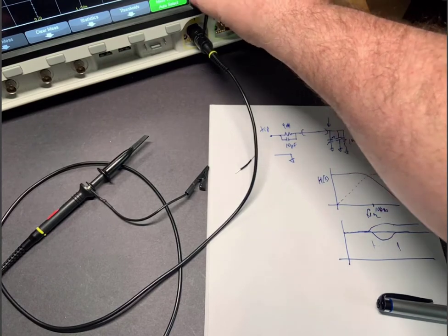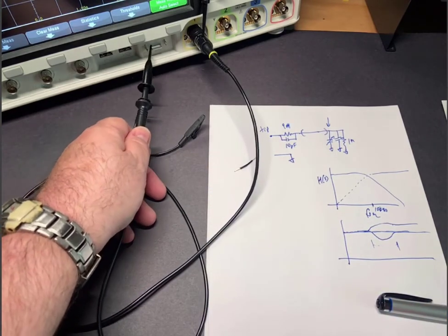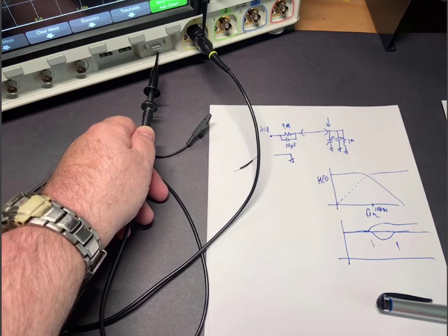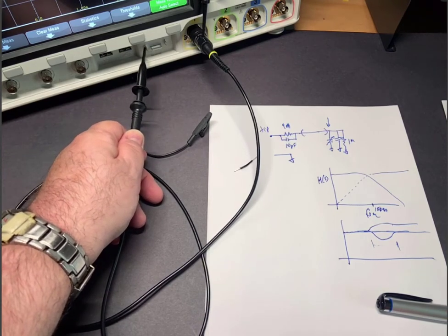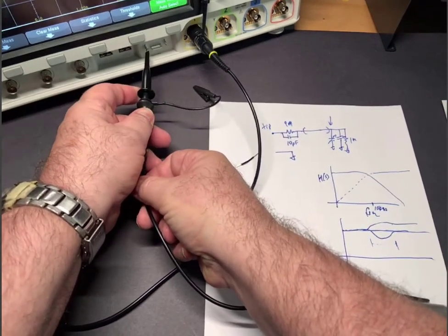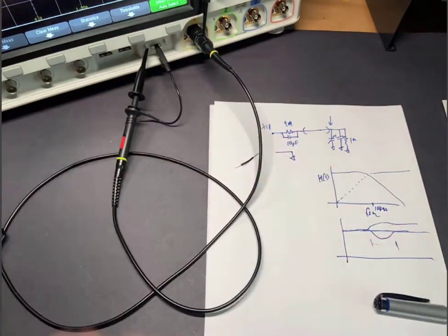So let's take a look at what the signal looks like from the compensation source inside the scope. And now, very important, when you look at this, there's the long bar, and it says underneath it, really hard to see, but it says that's the ground connection, and this is the probe compensation connection. So the tip is going to connect to the probe compensation signal, and the ground is going to connect to the large bar on the inside.